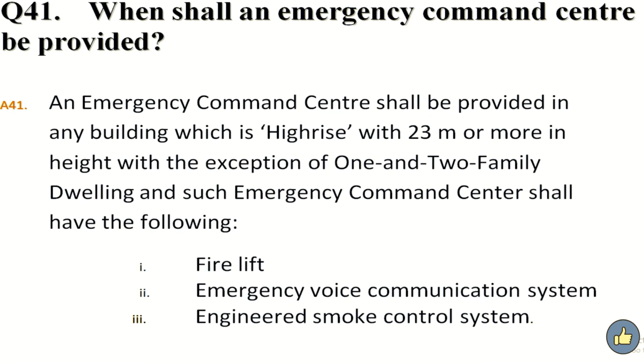When shall an emergency command center be provided? Answer. An emergency command center shall be provided in any building which is high-rise with 23 meter or more in height, with the exception of 1 and 2 family dwelling, and such emergency command center shall have the following: 1. Fire lift. 2. Emergency voice communication system. 3. Engineered smoke control system.